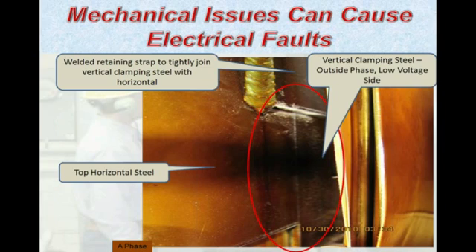On the A-phase coil here, the top left call-out shows the welded retaining strap to tightly join this vertical clamping steel with the horizontal piece. This is welded in place at the time of manufacture, and you can see the vertical clamping steel on the outside phase of the low voltage side to the right, and the horizontal steel is indicated by the bottom call-out to the left. This is all nice, even, flush, uniform, and a really good weld. It's the integrity of this type of joint that we would like to see.